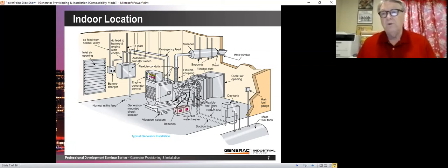Now you've got your flex fuel lines, and you notice the main fuel tank is down here. And so the suction line comes from the day tank into the generator. That's fine. But the return line goes from the generator back to the day tank. That is not where it should go. That makes the hot fuel heat up the day tank and can make that fuel too hot. Return lines, when the main tank is lower than the day tank, should always go back to the main tank, not to the day tank. And they, of course, don't show the pumping system there, so there's more complications.